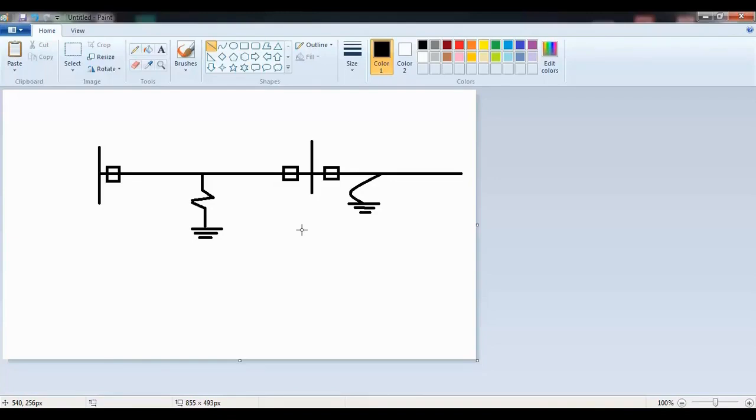To convert distance from non-unit to unit, use the distance communication scheme: overreach, underreach, unblocking, and blocking. Why? Because if a fault occurs on my line, I want to perform a trip operation. If the fault is within my line, I want to speed up the tripping process. This communication scheme interacts with our line, speeds up the process, and ensures the fault is internal.